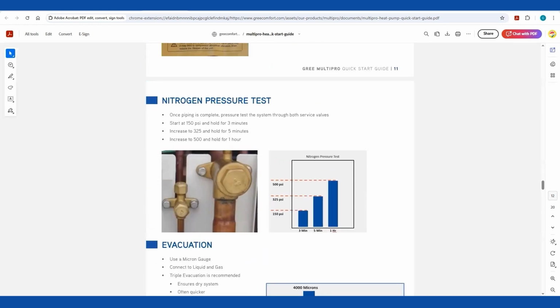Another thing I want to cover too is, before you start this thing up, let's do a pressure check. Make sure this thing holds pressure. So hit it with 150 psi of nitrogen. Make sure it holds for 3 minutes. Remember, you need to be putting that in through both sides of the system. I'm not going to guarantee you those indoor EEVs are open. Unlike a mini split, the EEVs are located in the indoor units. So when you're pulling a vacuum and when you're pressure testing, make sure you're charging the pressure into both lines and you're evacuating from both lines.